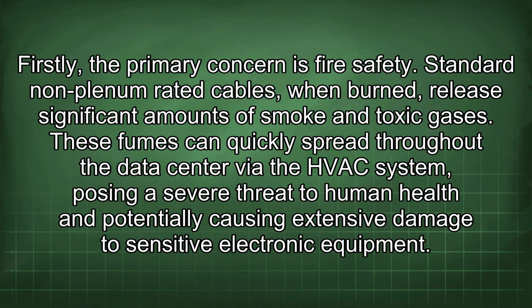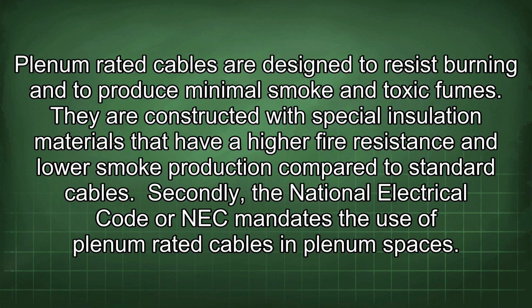Firstly, the primary concern is fire safety. Standard non-plenum rated cables, when burned, release significant amounts of smoke and toxic gases. These fumes can quickly spread throughout the data center via the HVAC system, posing a severe threat to human health and potentially causing extensive damage to sensitive electronic equipment. Plenum-rated cables are designed to resist burning and to produce minimal smoke and toxic fumes. They are constructed with special insulation materials that have a higher fire resistance and lower smoke production compared to standard cables.